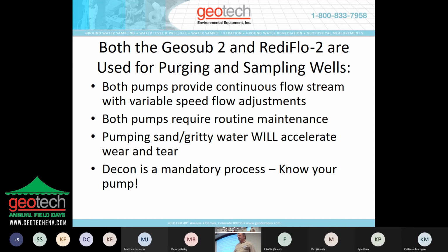Both pumps require routine maintenance. Over several years I've found that if you don't have the parts with you in the field, you're not going to find them at Home Depot or Ace Hardware. And if you think they're expensive on the front end, air freight to wherever your site is and a lost day is a little bit more money. Pumping sandy and gritty water will accelerate wear and tear. These pumps are designed for pumping good developed wells, clean groundwater, for purging and sampling purposes. I can't emphasize that enough because it's a real critical part to the longevity of these pumps.